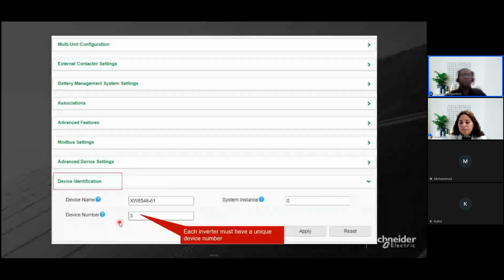5, 6. Just make sure that they're all unique, because you could have done all the settings correctly, but if you still leave this as the default device numbers, which come as 0, you're still going to have your F66, F69 errors. Everything must be unique. The device instance is not so critical. You can change it if you want to, but the critical one to change is your device number.